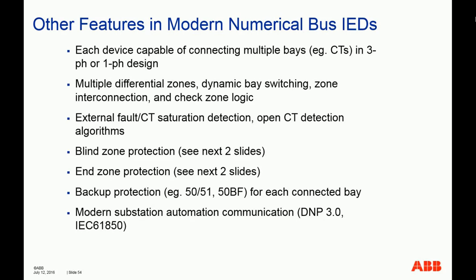But if you use the breaker fail protection inside the bus protective IED, then that information is already known and available, and it's calculated, it's processed by the bus protection algorithm because of the disconnect switch that you provided to switch the CT to the different buses. So those information is known. So when the breaker fail happens, it will operate and trip the right buses, trip the breaker, only the breaker connected to that bus, and not going to trip the other breaker. So this is a very important and handy function in modern numerical relays.